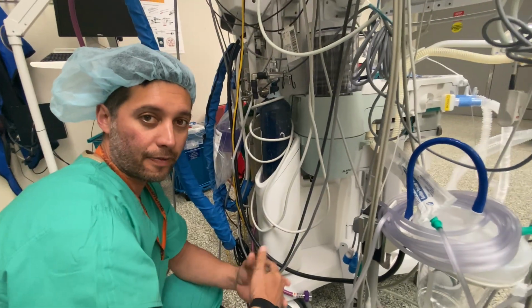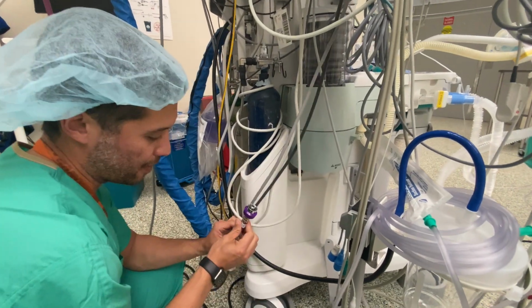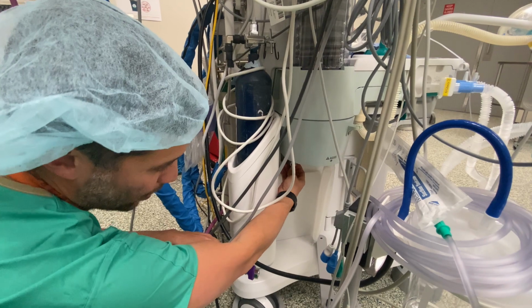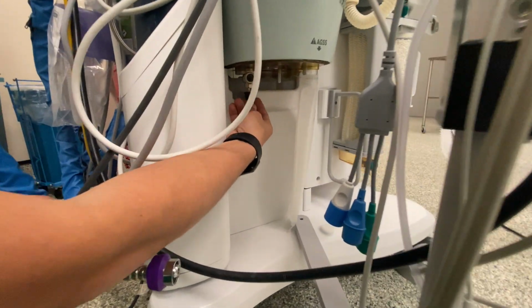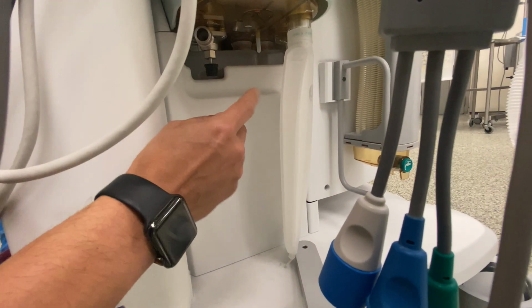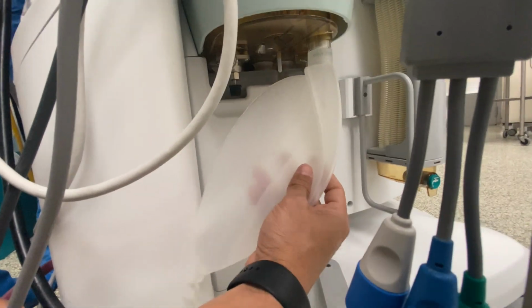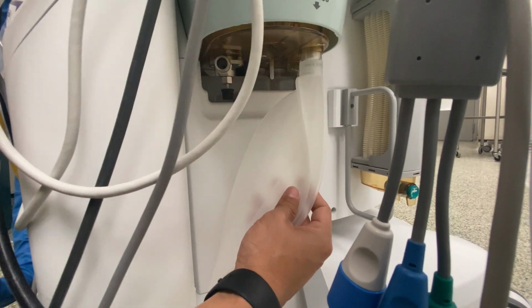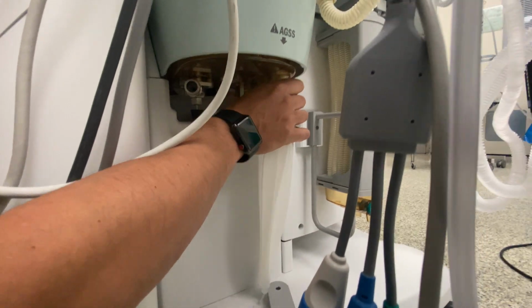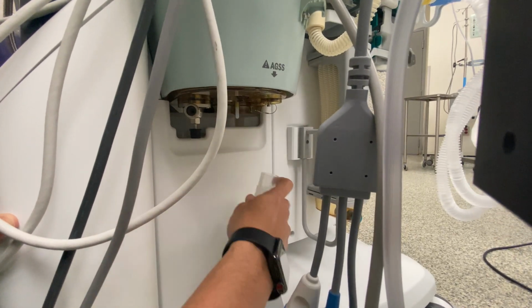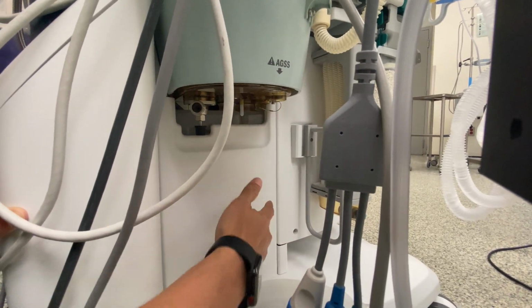All right, so all you have to do, if you disconnect the scavenging hose, there's going to be a buildup of pressure. We tried it, opening up this valve all the way. There's still about 10 of PEEP when this is connected. So if you have one of the bag type scavenging systems on your anesthesia machine, you'll have to disconnect it. And that's going to be all right because everything from the ventilator exhausts into the room.